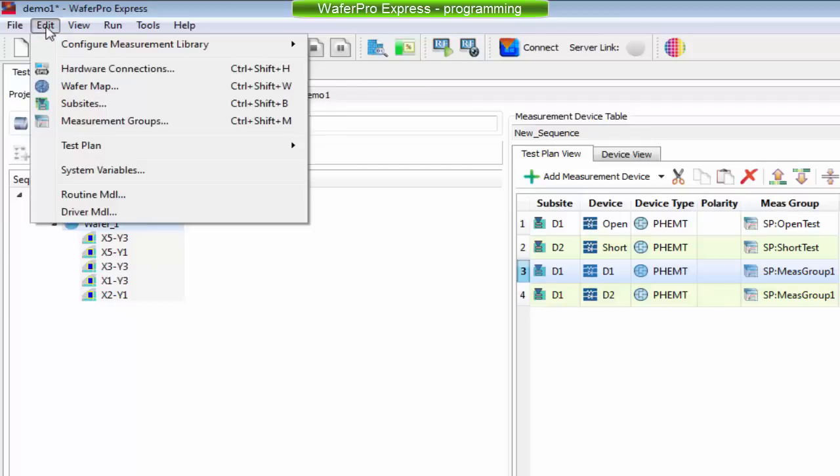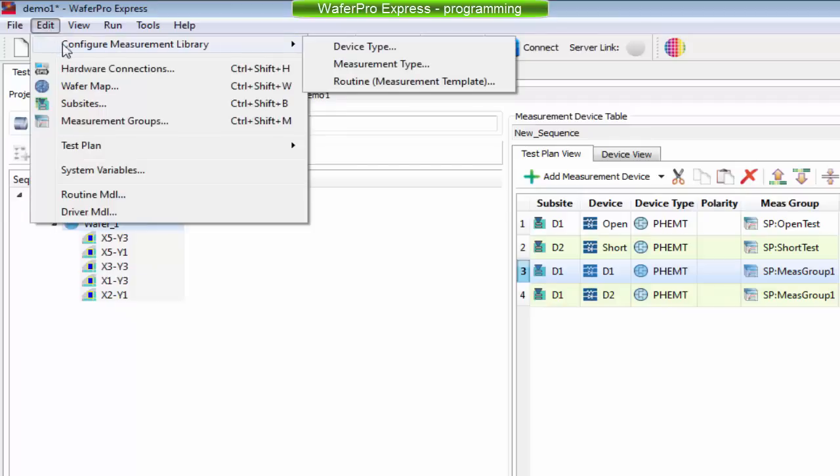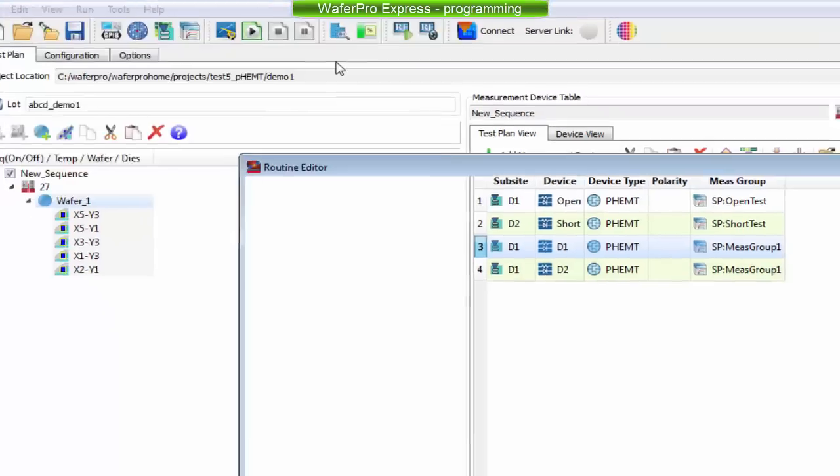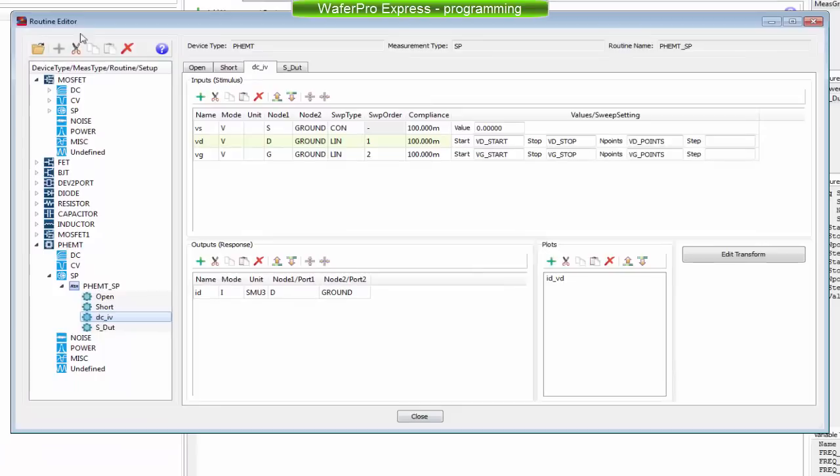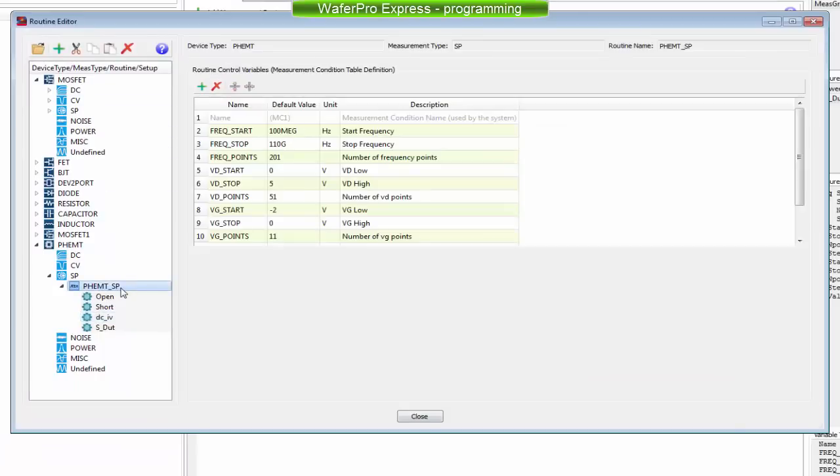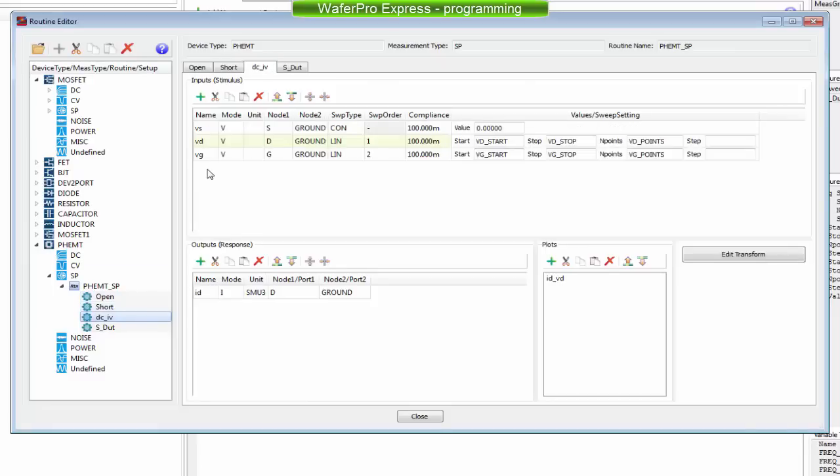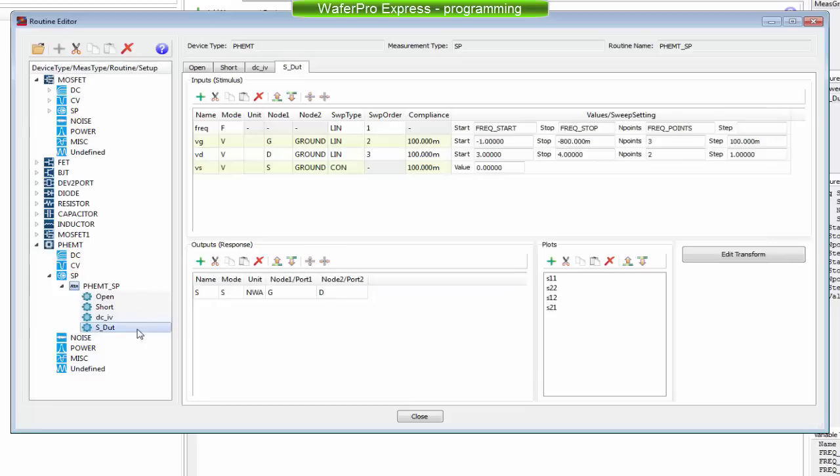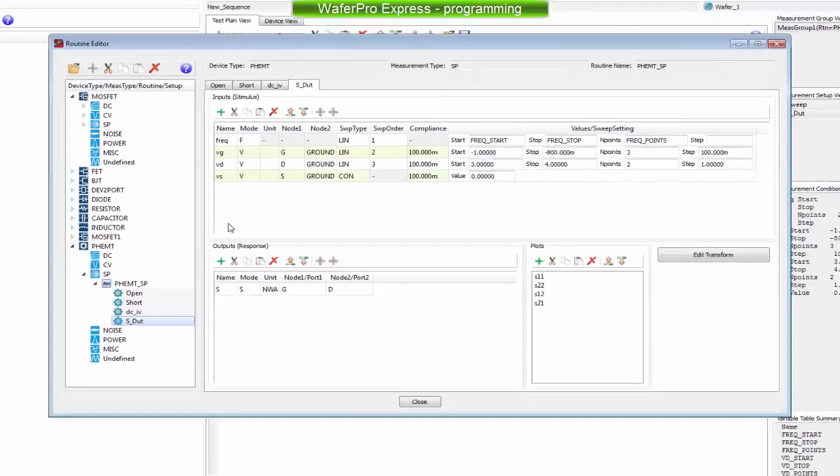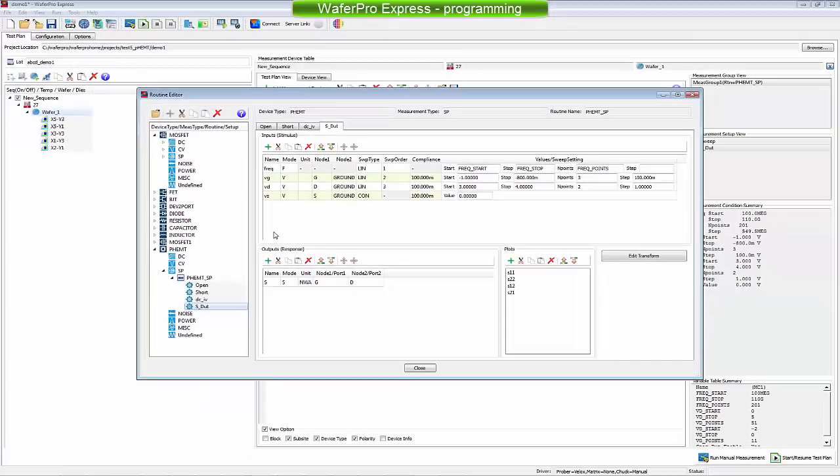In WaferPro, routines are organized in the Library Manager. The routine PHEMT SP includes four single tests, also called setups. The open and the short setups are just collecting S-parameters when measuring open and short structures. The DCIV test measures the IV traces. And the SDUT setup measures S-parameter versus frequencies at various bias points.